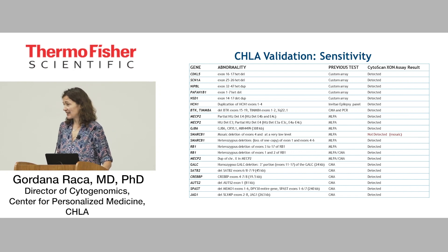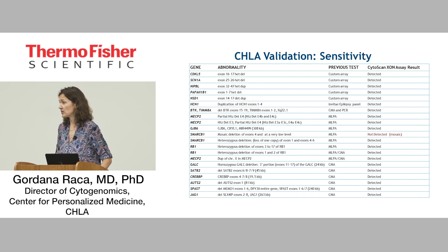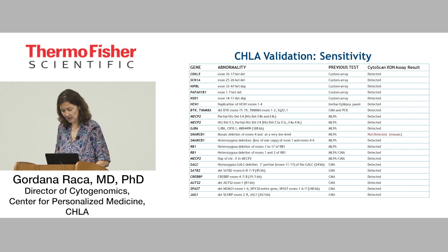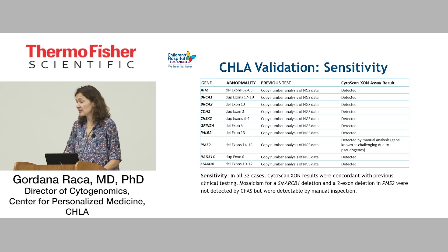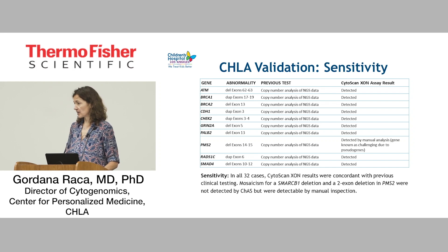We were very excited to test and validate the platform in our laboratory. We prepared a large set of positive samples with known, previously detected, very small deletions and duplications to test the platform's sensitivity. Those were detected by a variety of assays — real-time PCR and MLPA — and were specifically selected to be very challenging: one or two exon deletions and duplications. We were very pleased to see that in all cases the previously known abnormalities were detected. Two cases required manual review; all others were detected automatically by ChAS.